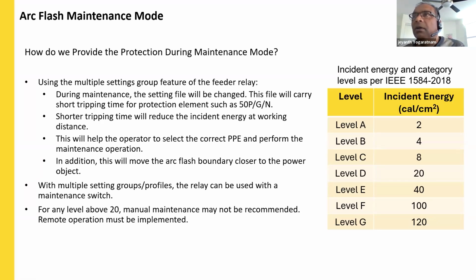And this table is from the IEEE 1584 standard, and there are categories of arc flash level based on the incident energy. Anything greater than 20, it is recommended to do remote communication to perform the operations.